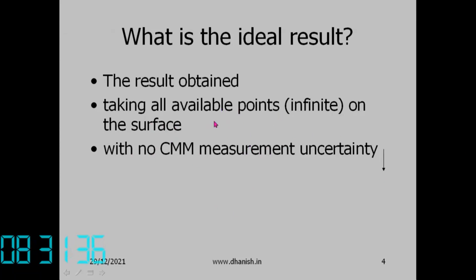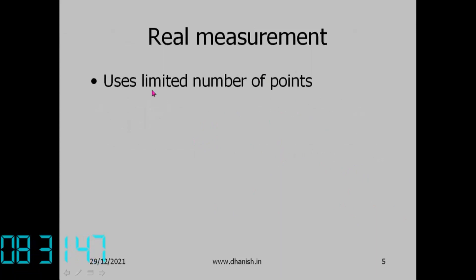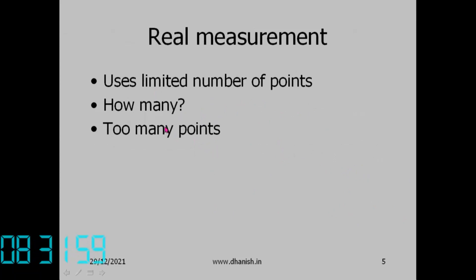In reality, you cannot take all available points and there will always be CMM uncertainty. So real measurement uses a limited number of points. Too many points takes more time, especially for a touch trigger probe where each touch-retract cycle takes time. After a certain number of points, more points give little additional change in result, so there is no need to take too many.